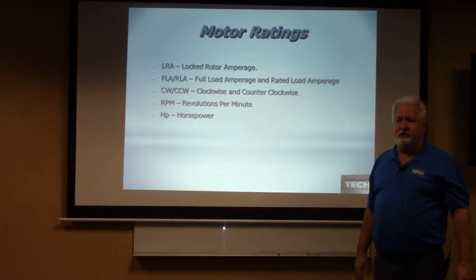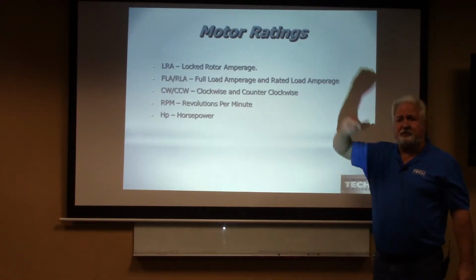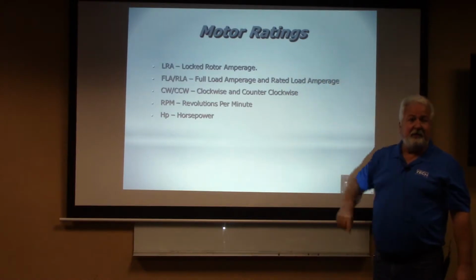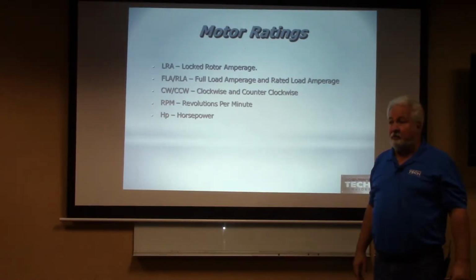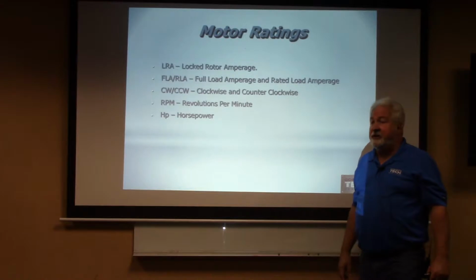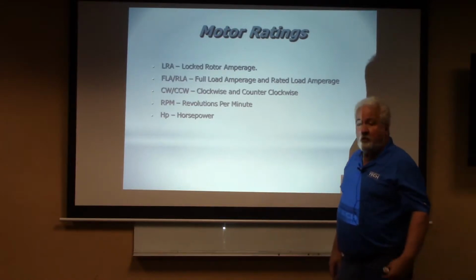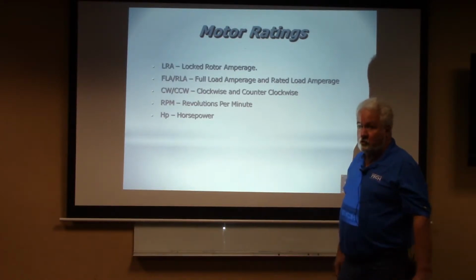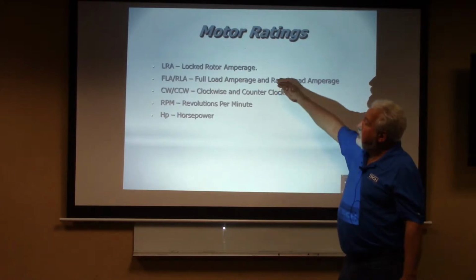Every time that motor starts up, it starts up from a dead stop. Is that right? If it starts up from a dead stop, you see the amperage jump up and then back down, because it started off at locked rotor amperage. So you'll see LRA on that every time. We don't want to see locked rotor amperage when it's trying to run and it's not.